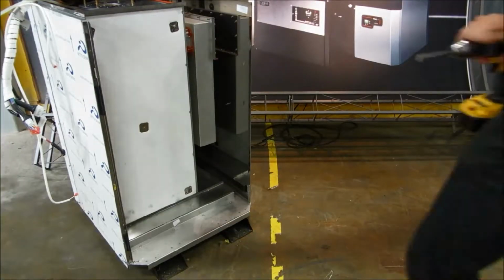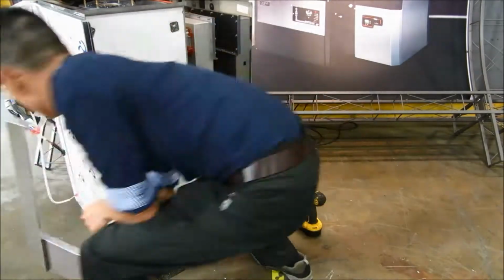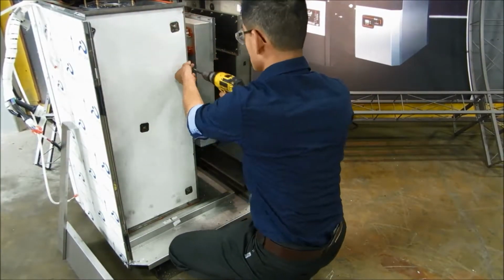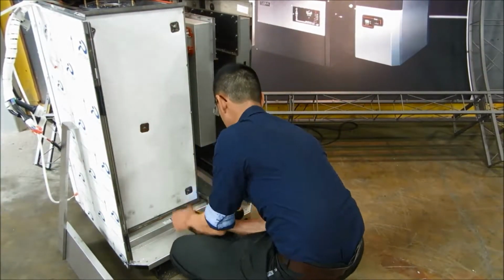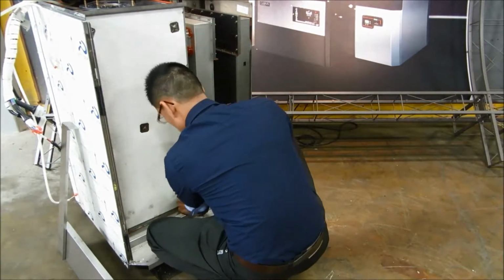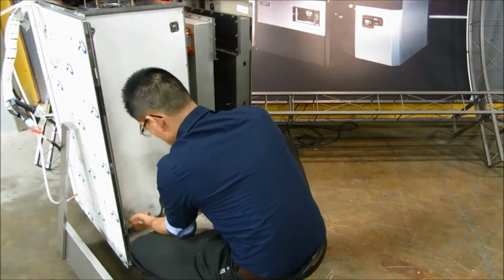If you find that cleaning is required, remove the front combustion chamber door. Use a 5/16 nut driver to remove the screws around the perimeter of the top panel. You may need to remove the condensate cover to remove the front combustion chamber door.